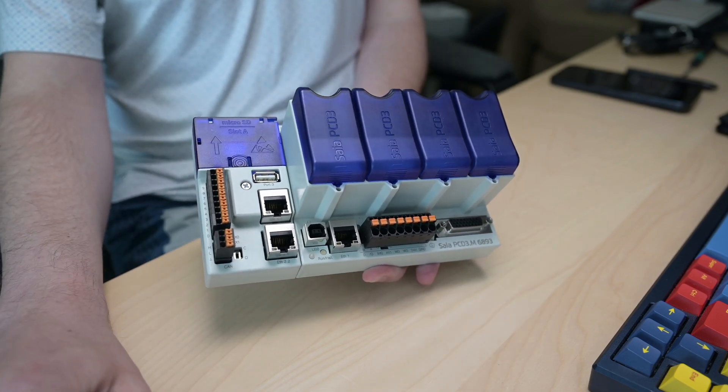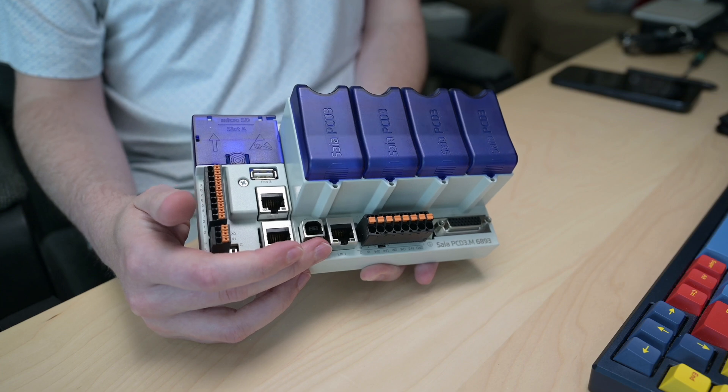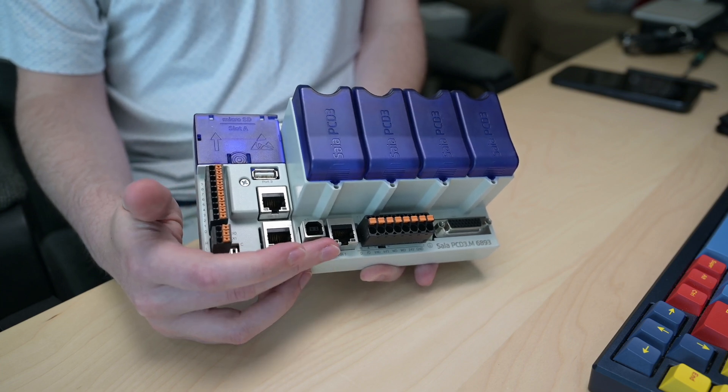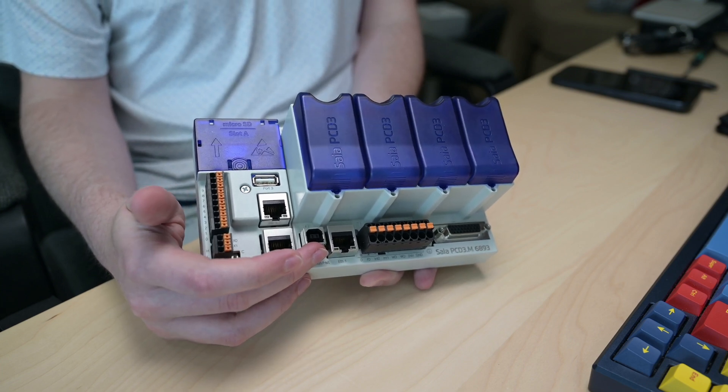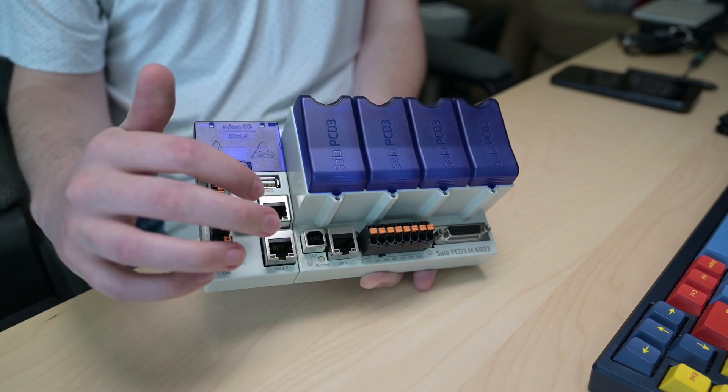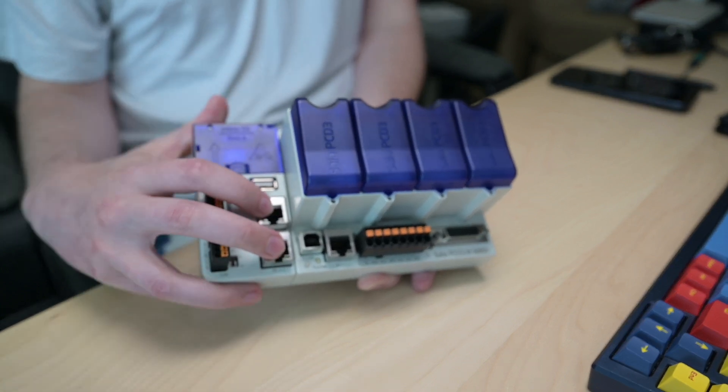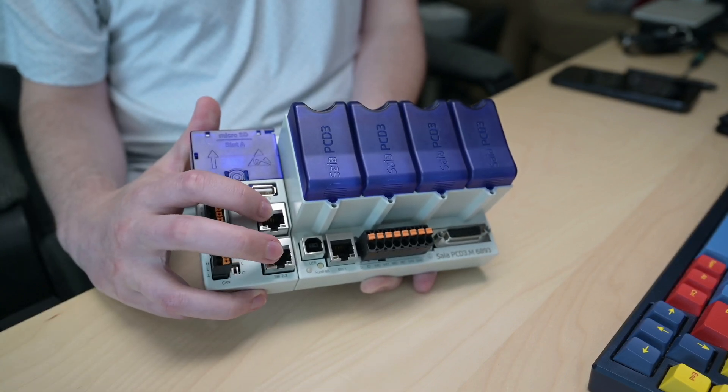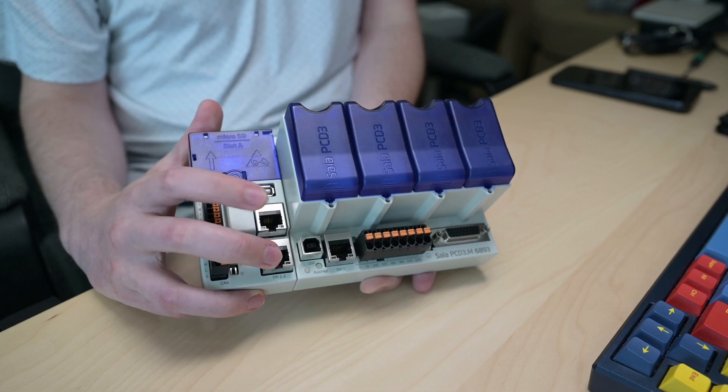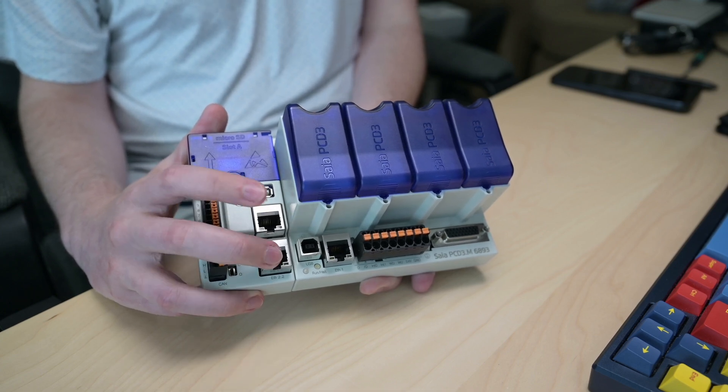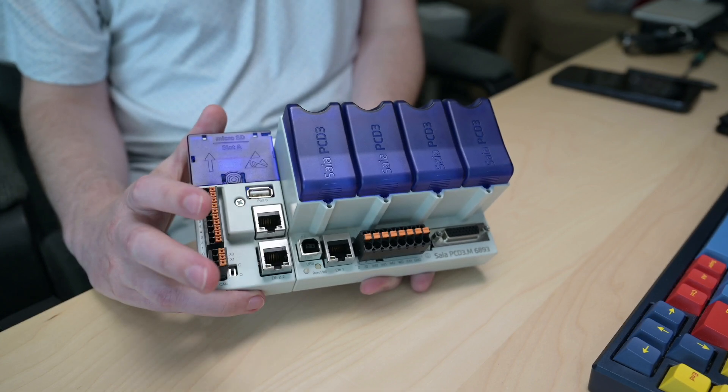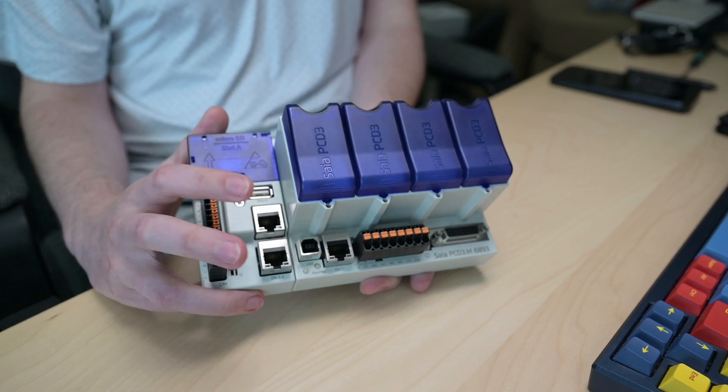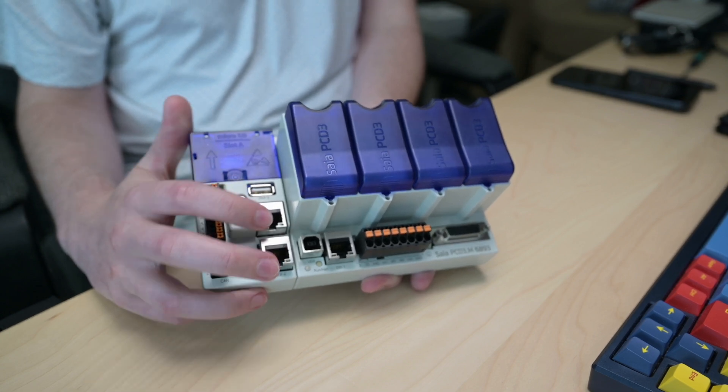Next to that, we've got an ethernet port. This is one of two ethernet interfaces that the controller has. The other ethernet interface is switched between these two ports. So don't plug into both of these ports expecting to get separate IP addresses or something like that. They are switched and they are going to go to the same network.